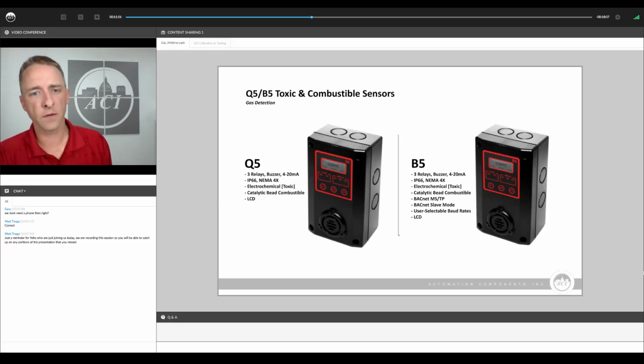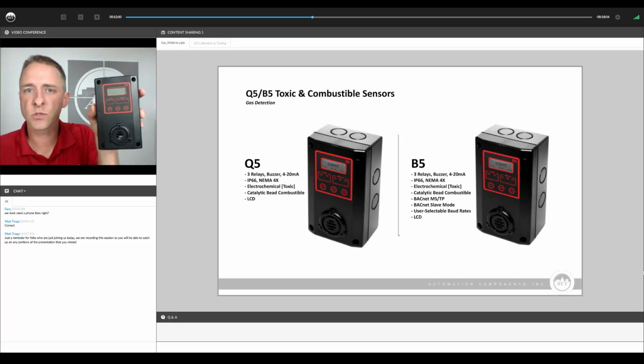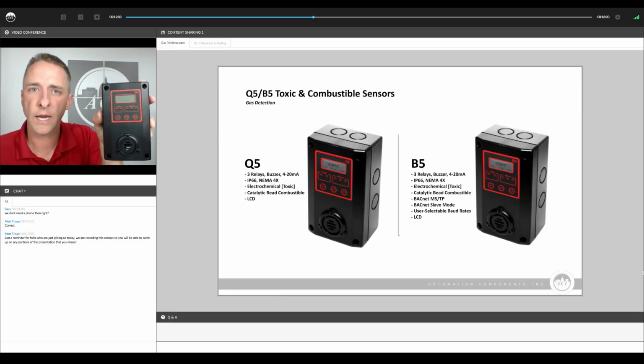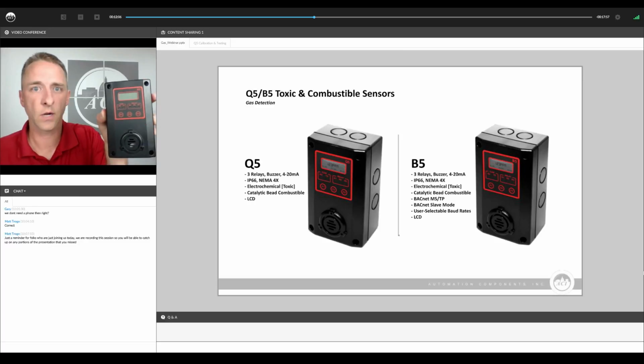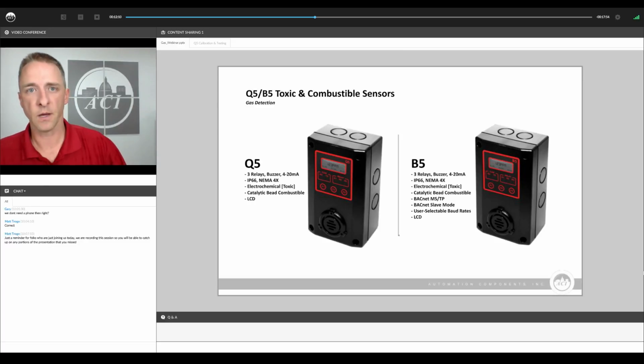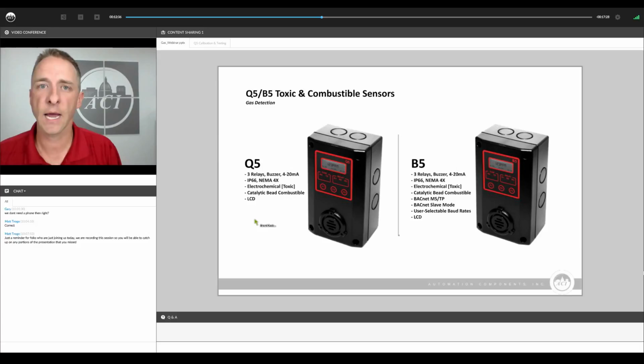Our Q5 and B5 series are shown here, and these are also available in a number of toxic and combustible gases, including but not limited to hydrocarbons, as well as ammonia, CO, NO2, hydrogen, oxygen, nitrogen, and a number of other gases. This gives you a nice compact NEMA 4X rated enclosure. You have 3 relays built in that operate independently of either the analog output or the BACnet output. That's the main difference between these two. The Q5 gives you an analog output in addition to the relays, where the B5 over on the right is in the same package, but it gives you a BACnet output in addition to the relays and the LCD display. And there's an audible alarm built in.